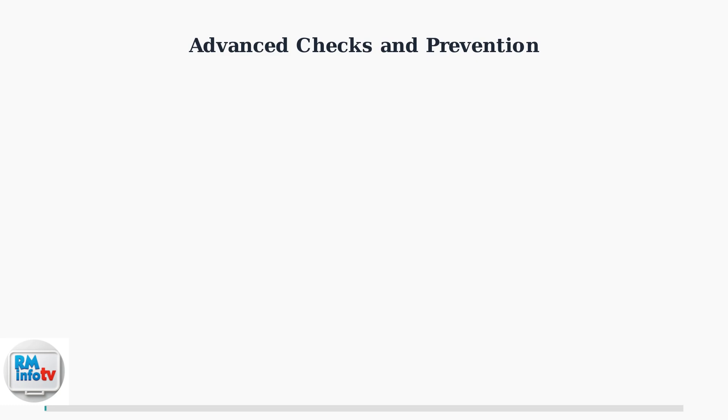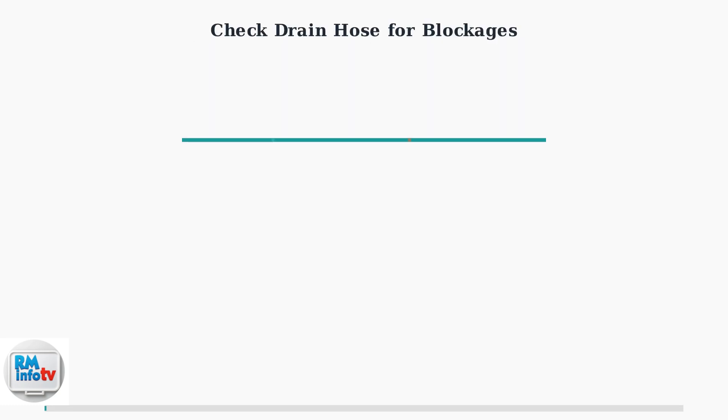If the FL error persists after basic troubleshooting, several advanced checks can help identify and prevent the issue from recurring. First, check for blockages in the drain hose if your unit uses continuous drainage. Remove the hose and inspect it for clogs, kinks, or obstructions that prevent proper water flow.